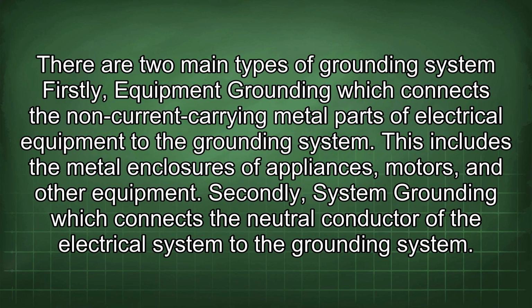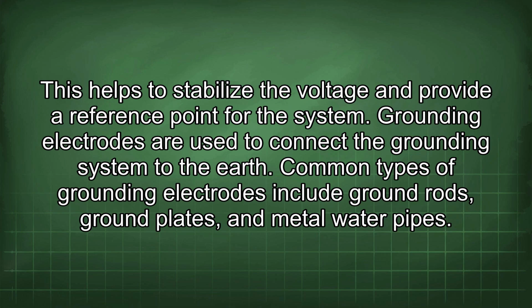There are two main types of grounding system. Firstly, equipment grounding, which connects the non-current carrying metal parts of electrical equipment to the grounding system. This includes the metal enclosures of appliances, motors, and other equipment. Secondly, system grounding, which connects the neutral conductor of the electrical system to the grounding system. This helps to stabilize the voltage and provide a reference point for the system.